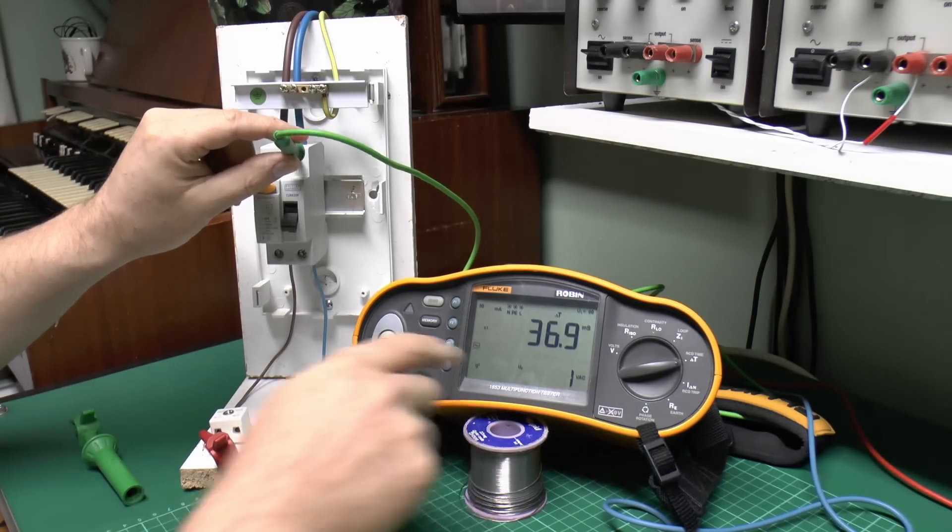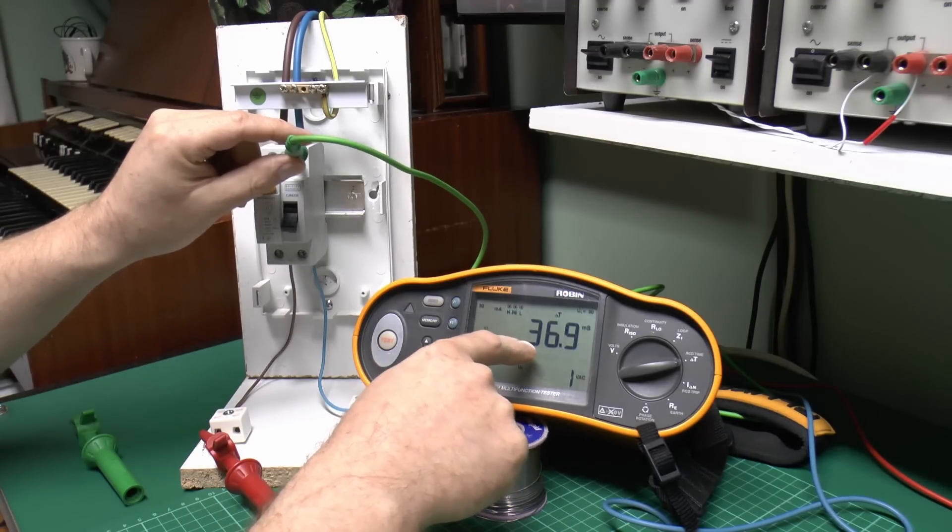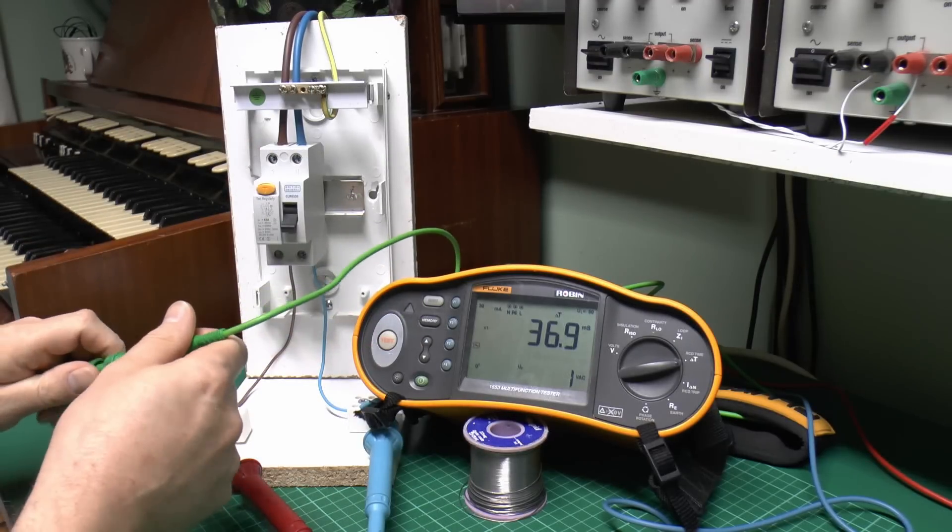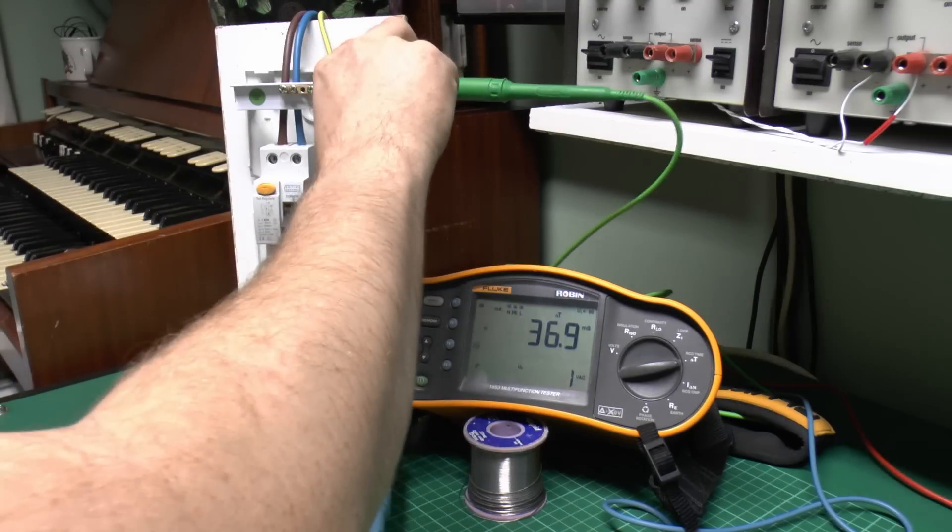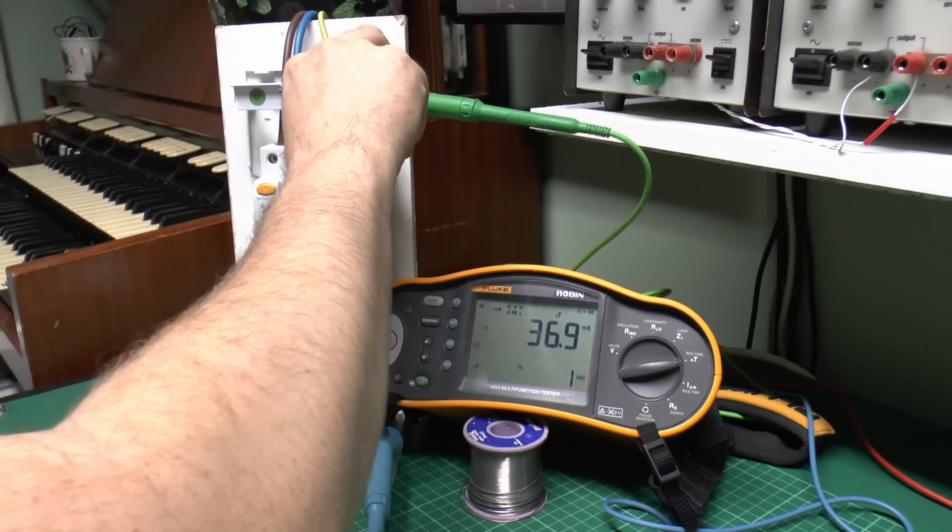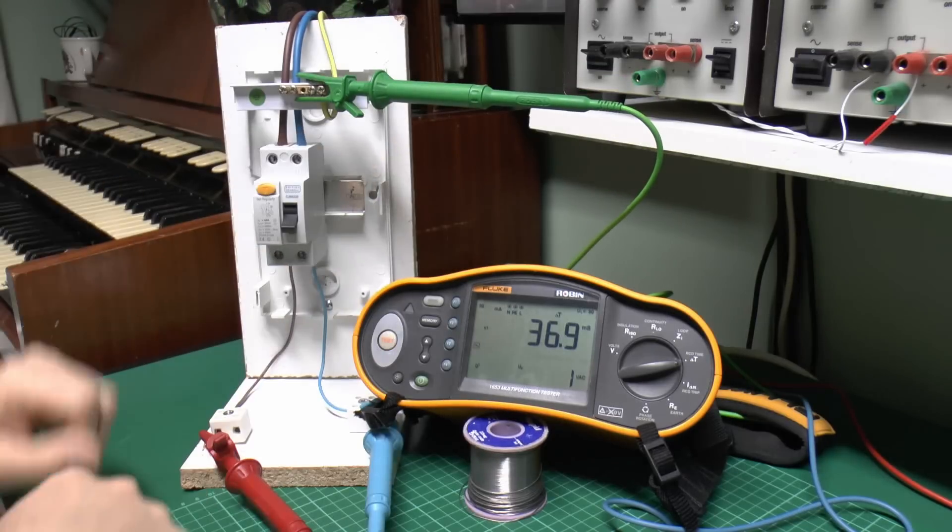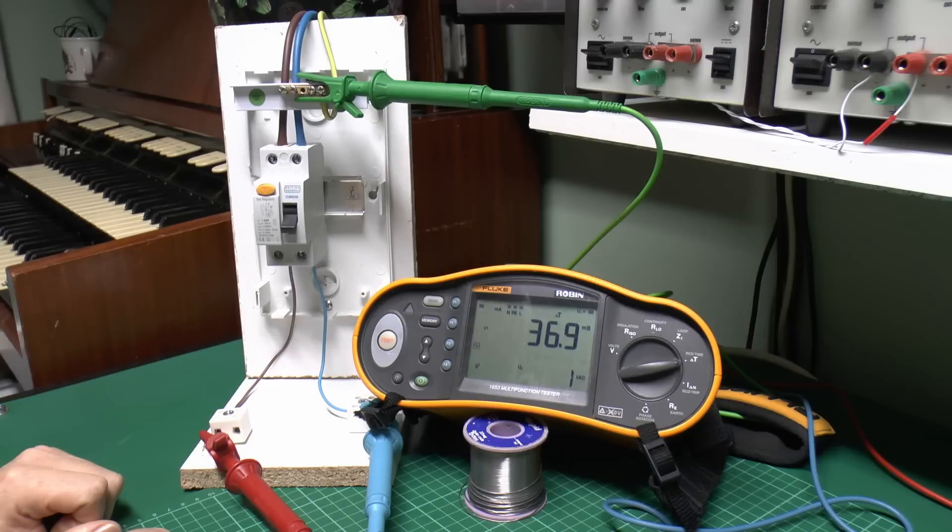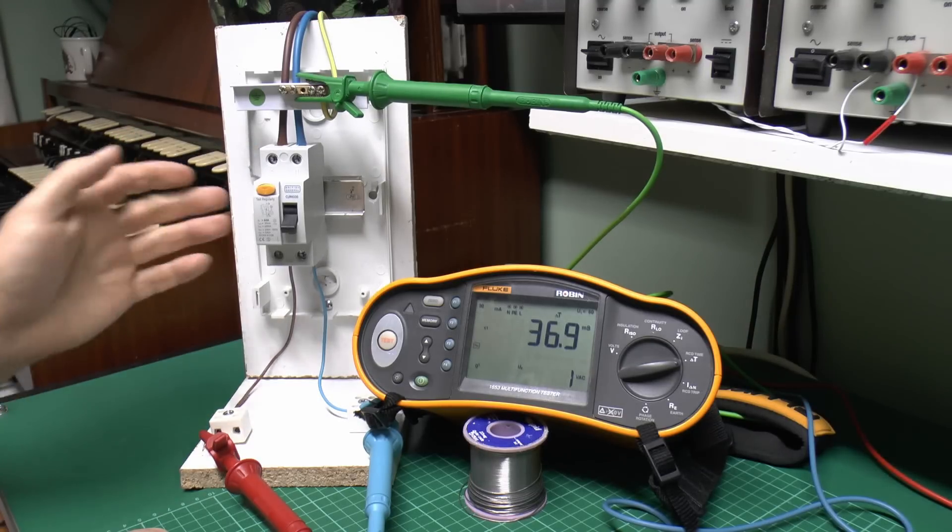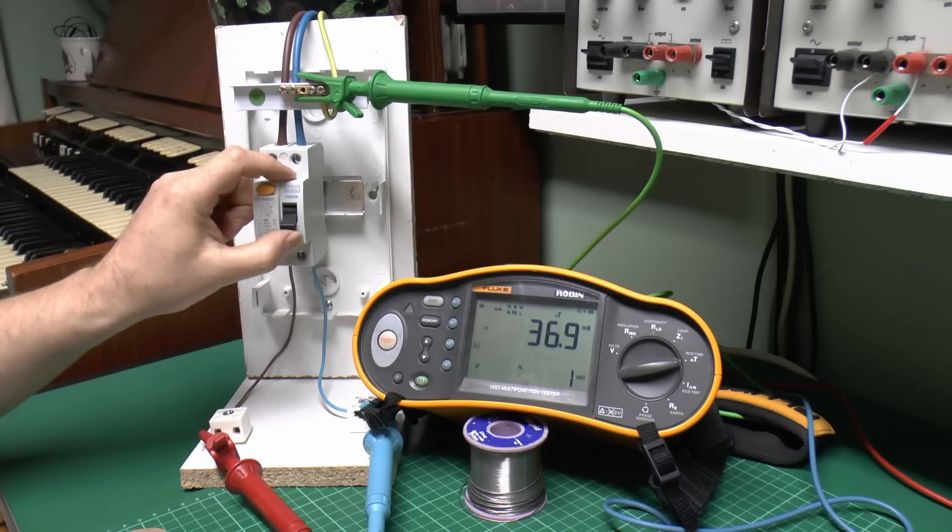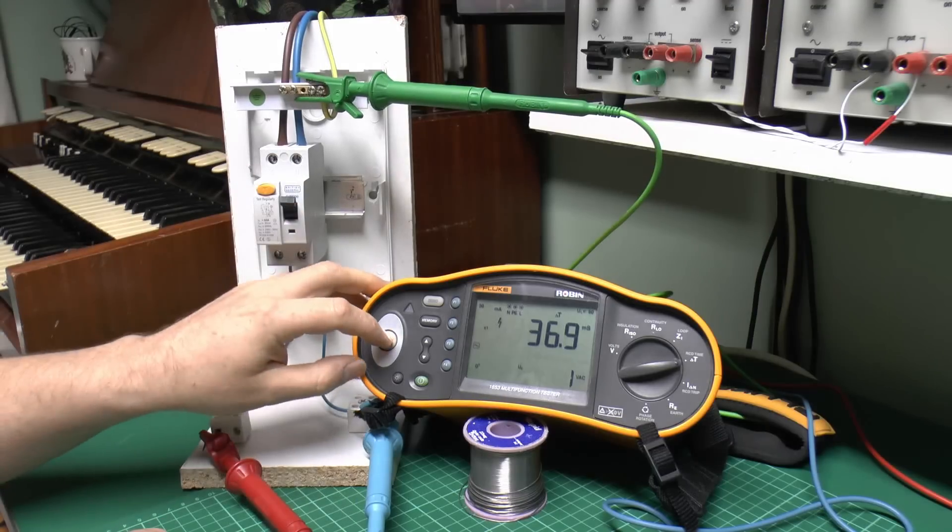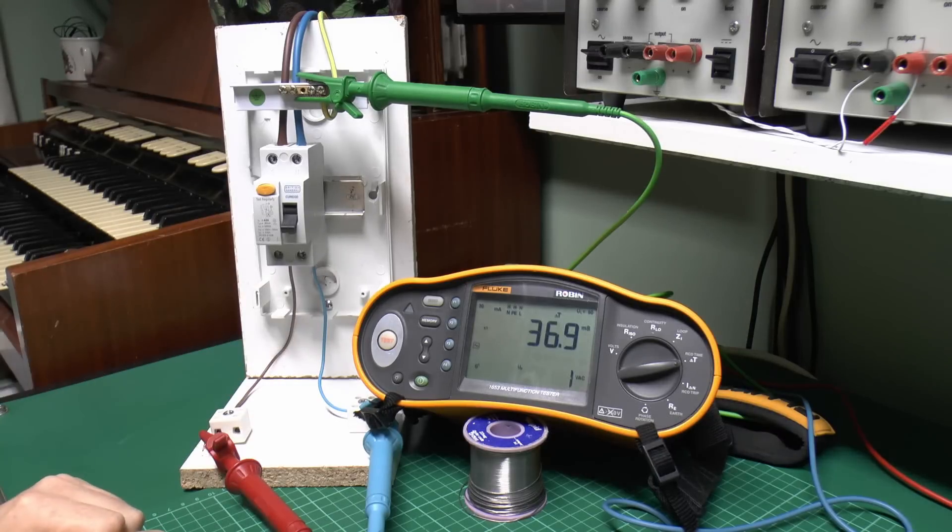Notice that the test result here is actually slightly less than we had before, it was 39.2 previously and it's 36.9 there, and again that's a fairly common situation. It will vary slightly depending on the exact circumstance you're testing it in, things like temperature and whatever else can affect it, and also how often it's been operated previously. If it's been installed for say five years and no one had even bothered to press the testing button for that time, it's quite likely the mechanism might have got a bit sticky, and you would expect therefore it to take a bit longer to trip. But in this case we've used it several times there so it may have actually loosened up a bit when we do it, so now see it's doing that 36.9 fairly consistently.